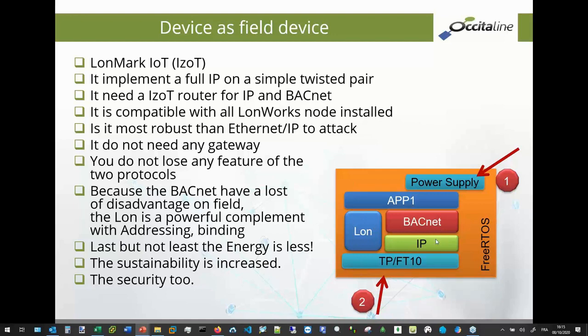The new generation of devices in IzoT, LonWorks IoT, implement, in fact, on a twisted pair, a simple IP stack, a BACnet stack, and a LON stack just behind. And the application is on a very simple operating system, and the messages arriving by the field are limited, like we have the limitation on a simple LON or a simple Modbus or a simple MS/TP device.